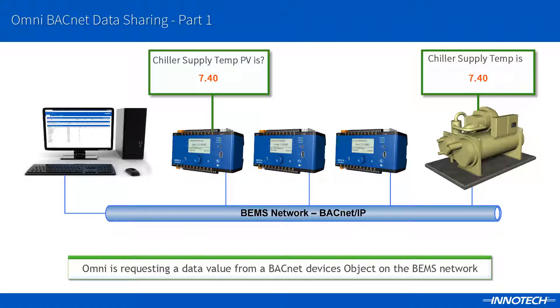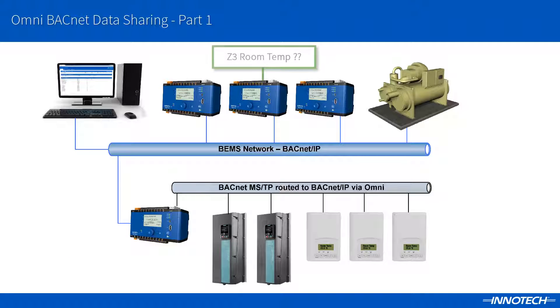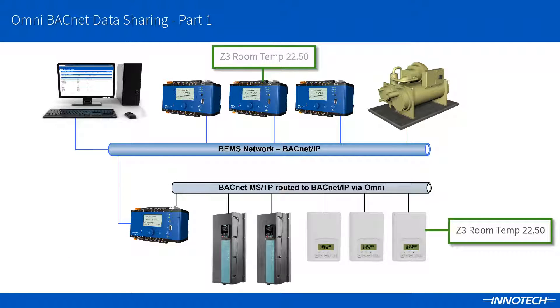There are many properties available for each BACnet object. Usually the most common property type used will be the object's present value, in this case the temperature value. The devices can also exist on a BACnet MSTP network segment that is routed back to the BACnet over IP network. We can target any device and its objects, as the network is seen as one BACnet over IP network.